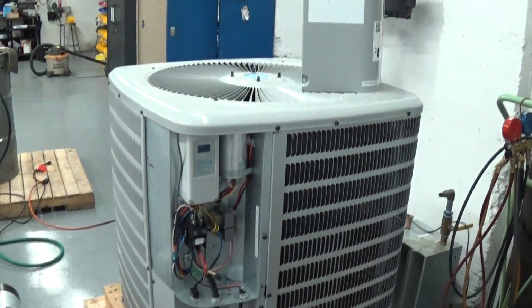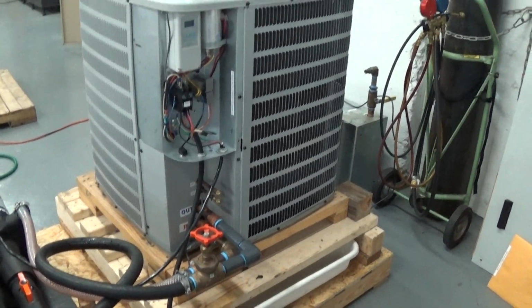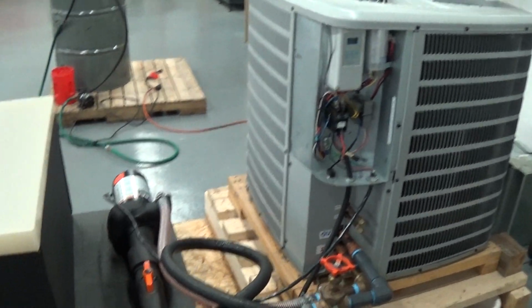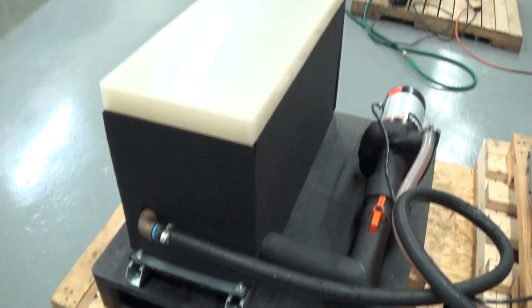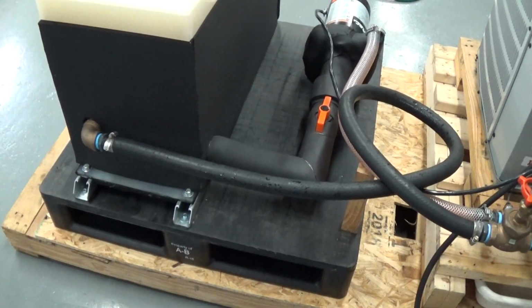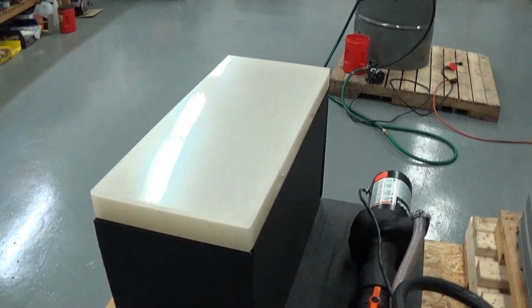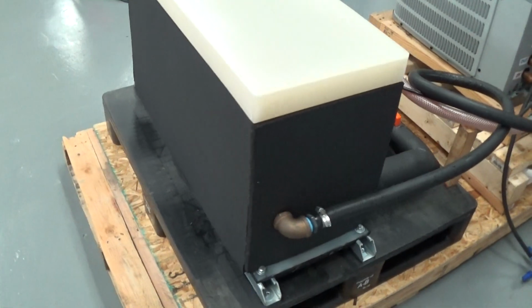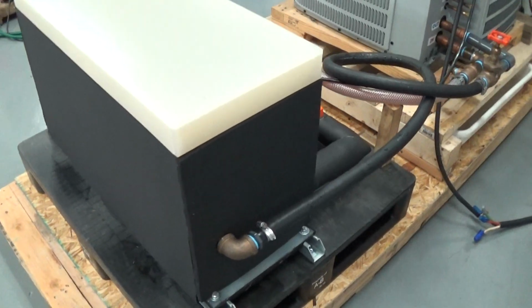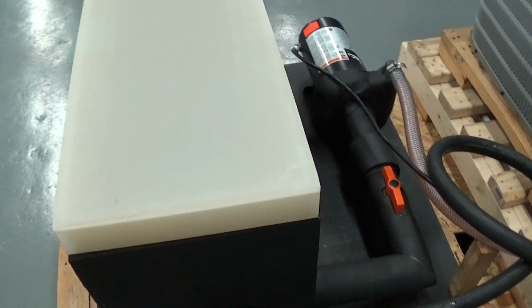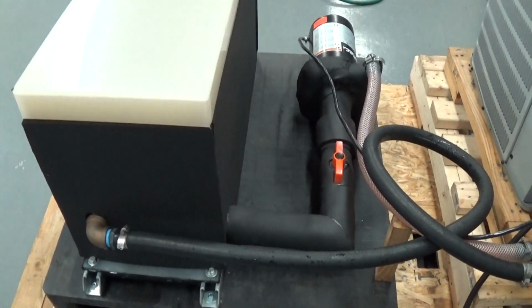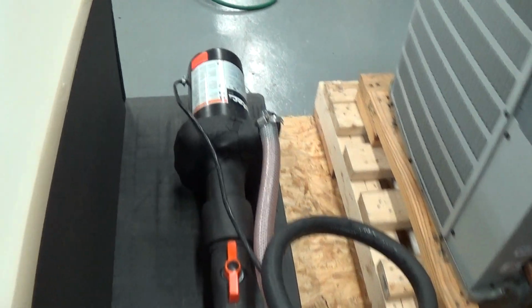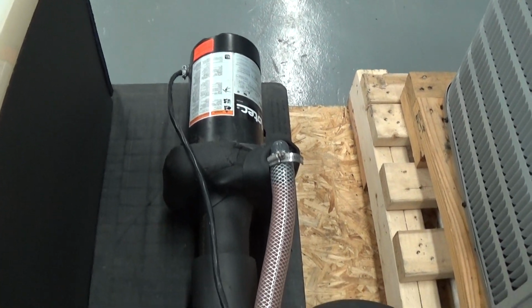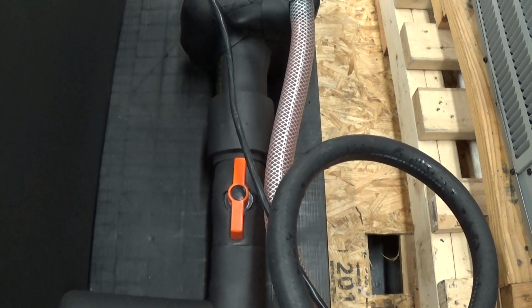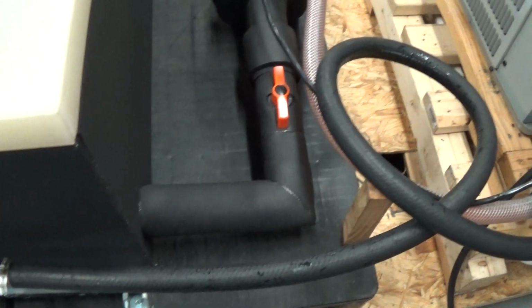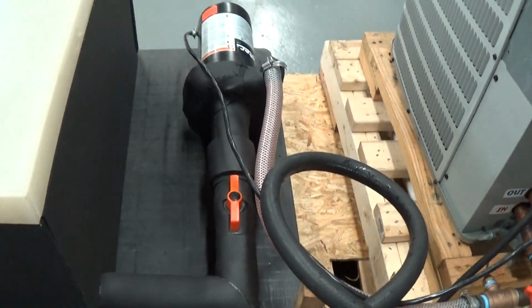And the idea is this is a very economical setup, an extremely economical setup, if a customer wants to do the pump and a remote glycol tank on their own. In this case, we did it for our customer. This is an approximately 35-gallon glycol reservoir, insulated on the sides and on the bottom. It does not need to be insulated on the top if it's just a lid, because it's not in contact with the glycol, FYI. We have a nice 1 horsepower centrifugal pump here, and we have a shut-off valve that should remain open at all times when running. That's strictly just for service.